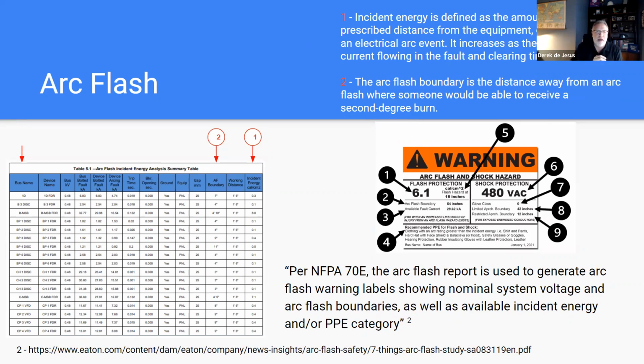There are other boundaries listed on here as well, such as the working distance, such as the gap required between equipment and phases. So there are different ratings and different requirements on this table, but I just highlighted the first two that really pertain to anyone that works in or around an electrical room that's energized, specifically in a construction environment where you have many trades meandering in and through an electrical room or near a transformer vault where there could be an arc flash hazard.